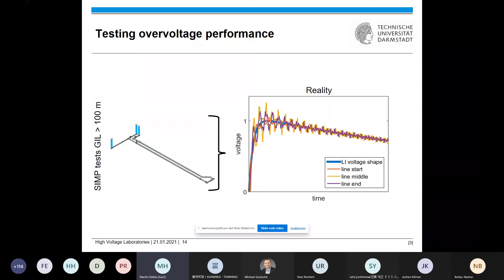And well, the easiest approach is that you use higher front times for the testing, and there are two possible solutions to achieve this. You can make higher front times with a conventional lightning impulse, or you can make higher front times also with an oscillating impulse. Here, both oscillograms are shown. Some words for oscillating impulse voltages: they are used for on-site testing. So when you make impulse testing at site, the generators for this testing are quite compact.